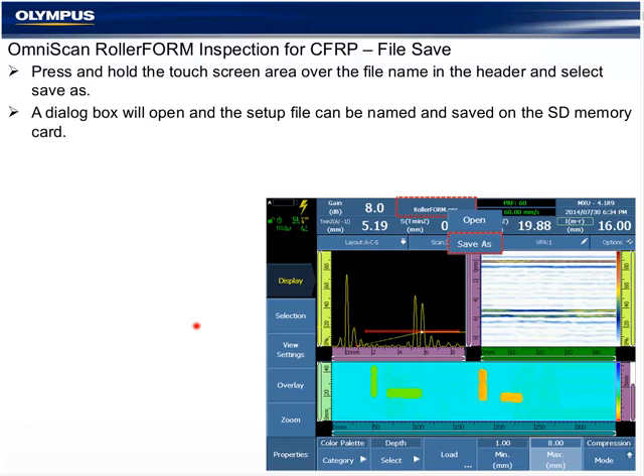So at this point, our configuration of the OmniScan, not including the hardware from the RollerFORM yet, is complete. The phased array was configured for a linear 0 sector scan using all 64 elements of the probe. Our gate mode position was optimized. We are in A-scan synchronization mode that was determined from our yellow gate I, and we saved the file by a press and hold on the file name area of the OmniScan header. Select Save As, and a dialog box will pop up to allow us to save the file on the SD memory card.